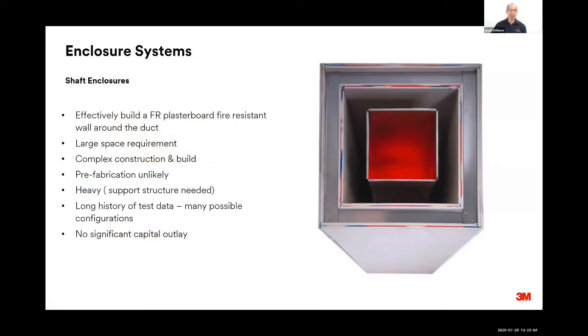So I'll just quickly touch on some of the different types of fire-resistant enclosing construction. A shaft enclosure with a plasterboard enclosure is an effective way of separating the duct from the rest of the building, and effectively involves building a plasterboard fire-rated partition around the duct. But it requires quite a large amount of space to achieve this, and it can be complex in the construction and the build. Also, the space available is usually quite limited. And in general, prefabrication is not very easy to do, so it all has to be done in situ.